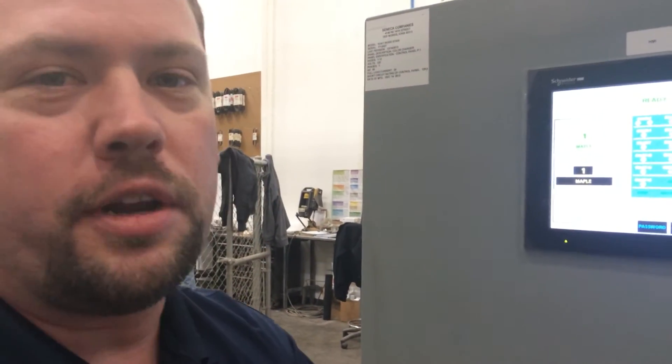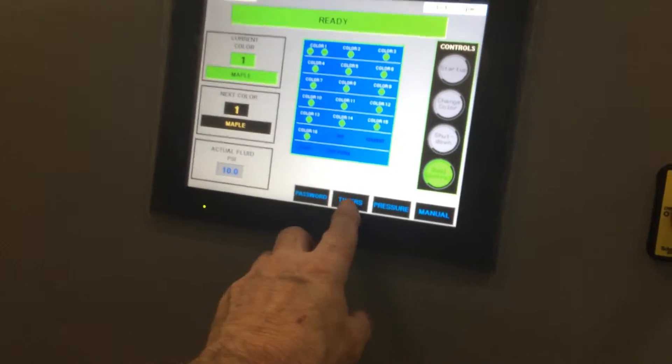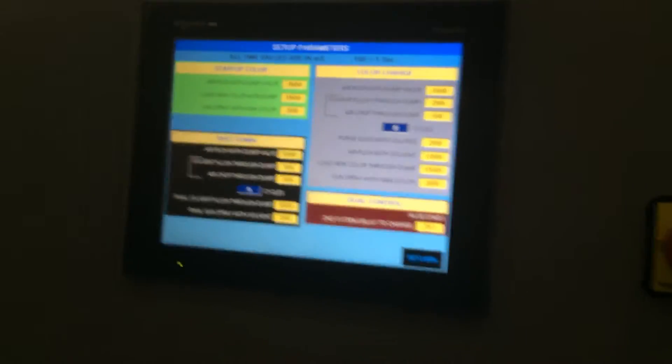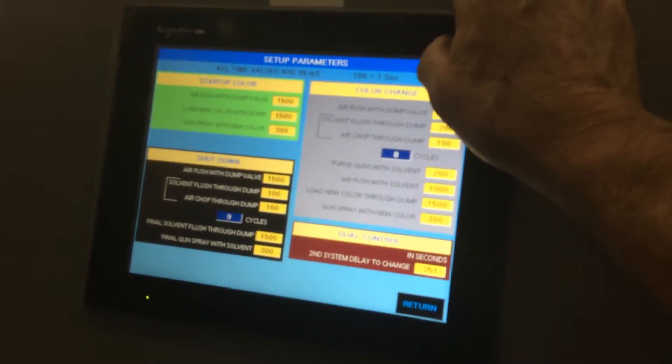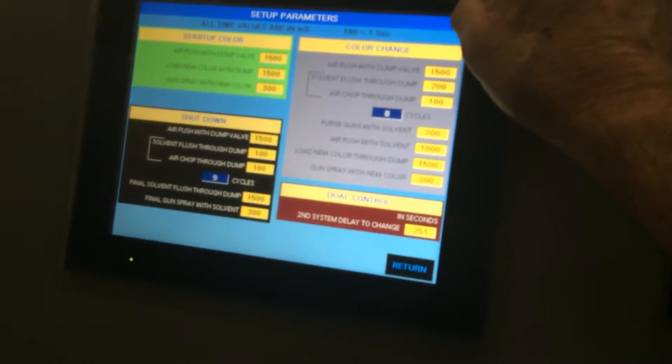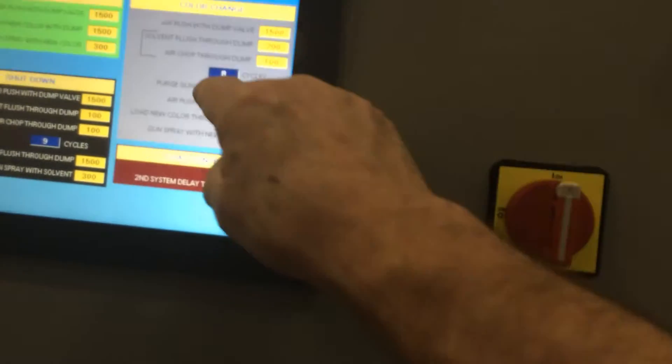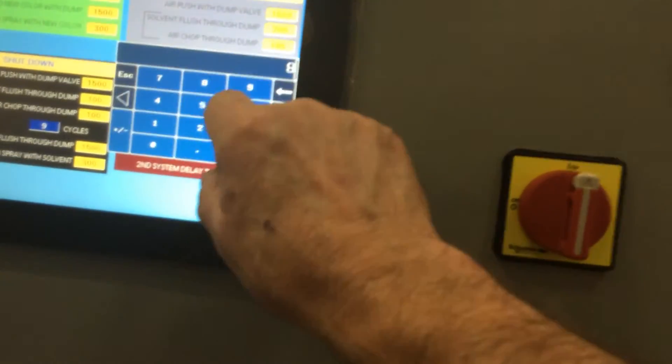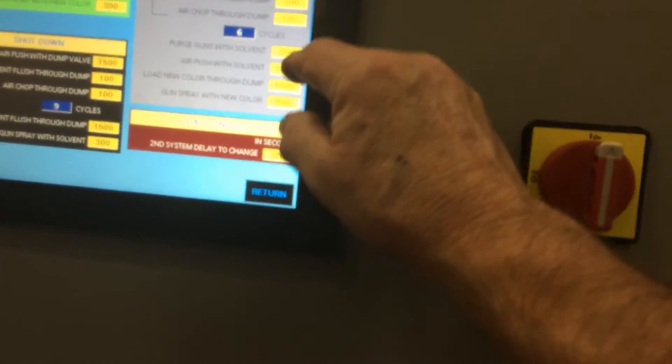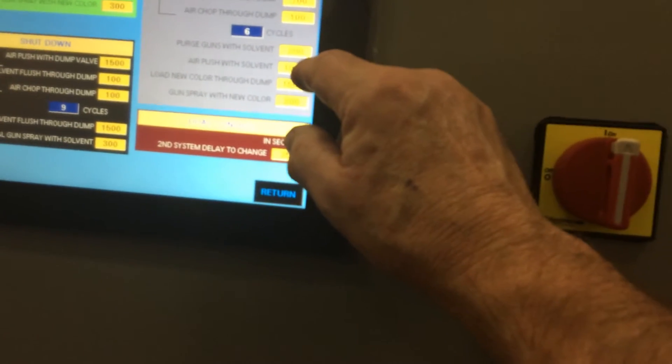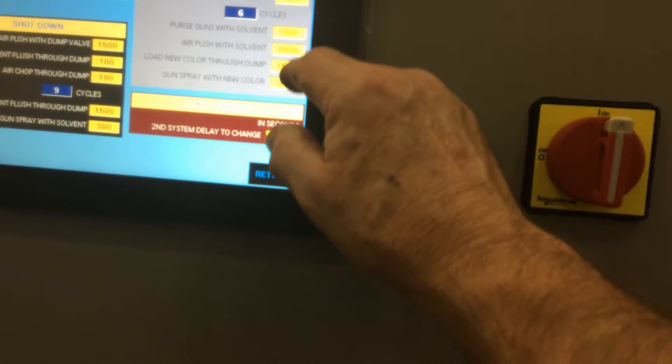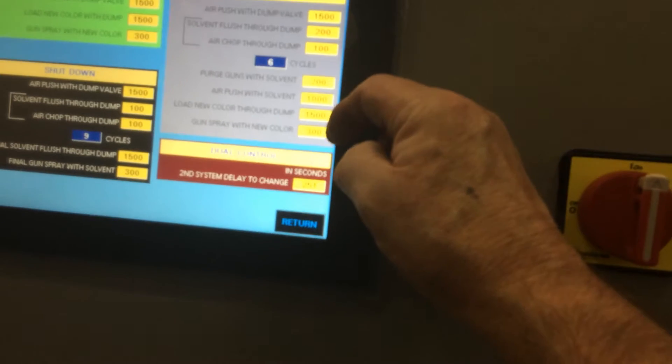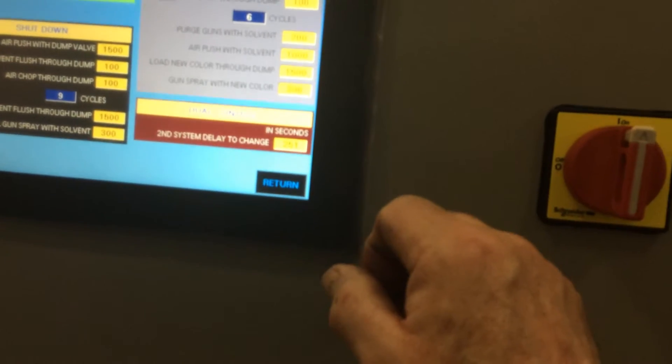So what we've shown you today is going to require the password to get into it. As far as the different setups, the load at the beginning of the day, what we're doing is we're doing a purge of the air. Since everything is full of solvent, then we load the new color, and then purge the guns. During the day, we push the solvent that's in the guns out, then do a chop, and we do it by whatever number of cycles you want. You can do it six cycles. After you do a chop and clean the lines, and you purge the guns, then you push the solvent out with air, then you load your new color. You always want to purge the solvent out before you load the color, otherwise you're going to dilute it. And then with the new color, you purge the guns.